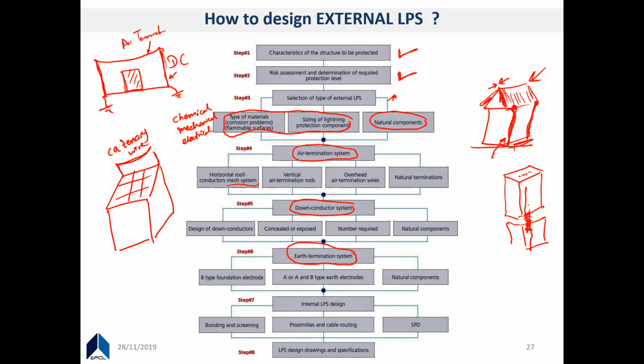Okay, so in a substation, that's what you see. Your lightning protection system is not installed on transformers, circuit breakers, CTs, PTs. It is not installed on that substation equipment, but you have separate air termination, these catenary wires mounted on top of steel lattice structures in the substation. Likewise, if you have certain storages with explosives, you can have this isolated system. We call this an isolated LPS. Depending on the application, you can select whether you go for an isolated LPS or a non-isolated LPS. So these are the types of air terminations you can use.